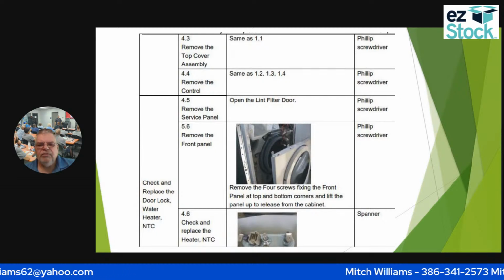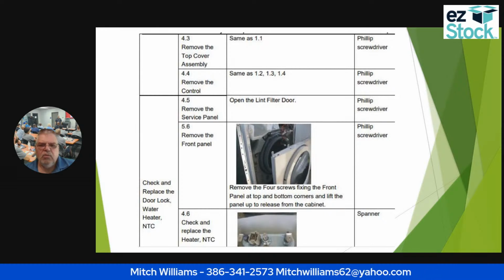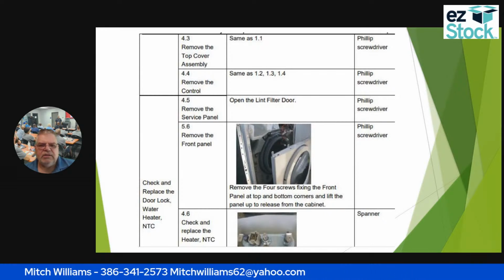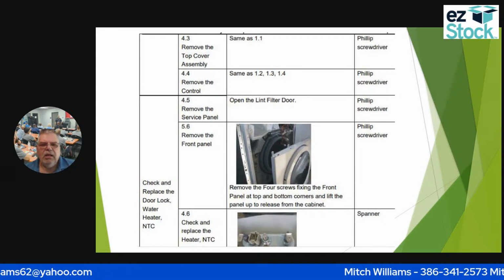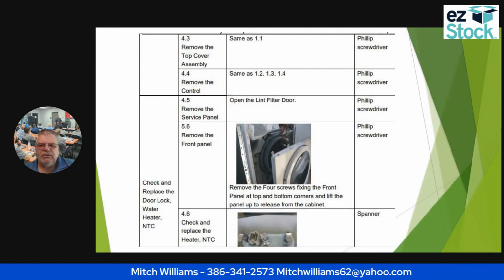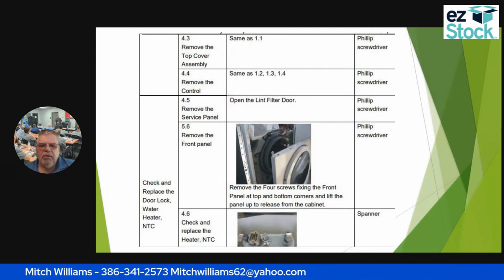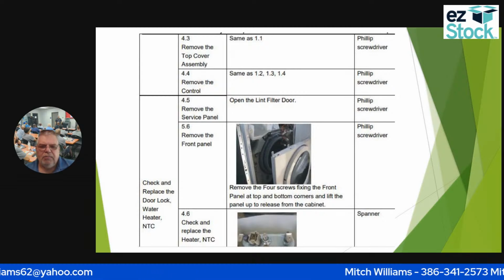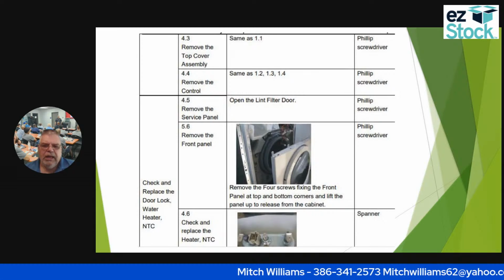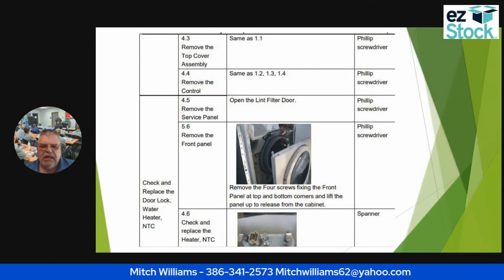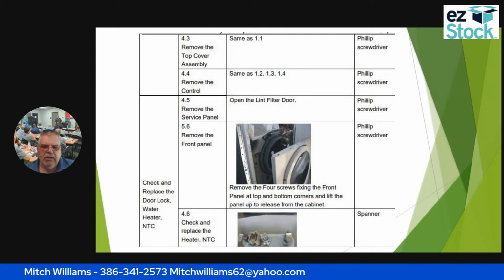Okay. To remove the top cover, we do the same thing. You see it right here. We've already talked about taking the top cover off. That was those two screws at the back, and then I'm going to slide it back out. Then I'm going to remove the control panel. Once I do that, I can remove the service panel. Then I can remove the front panel, which you see right here. Remove the 4 screws affixing the front panel to the top and bottom corners and lift the panel up to release it from the cabinet. Then I can check the NTC and the heater from here.